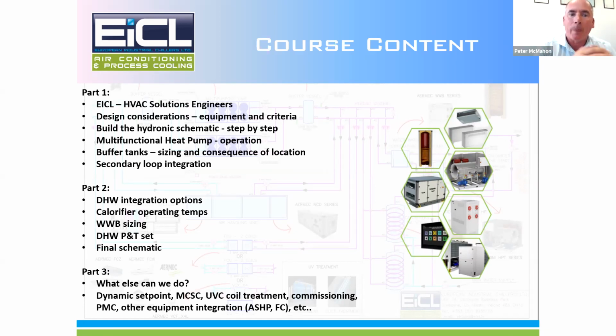We're representing the manufacturers. So anyway, I'm going to focus today on multifunctional heat pump technology, so you understand how it operates and the benefits of it. It's a water-based system as opposed to a DX system, that's DX refrigerant. I'm sure a lot of you will have DX systems installed. I'm also going to mention the importance of volume in your water system. Very, very important. And the location of that buffer tank, depending on where you put it, can have an effect. And I'm going to tell you one or two other things we can do to improve the efficiency of your heating or cooling system.